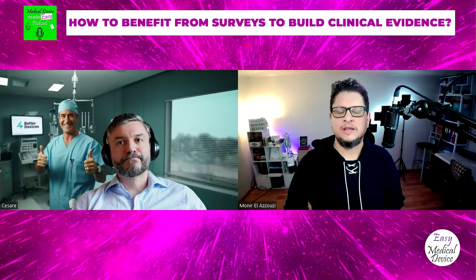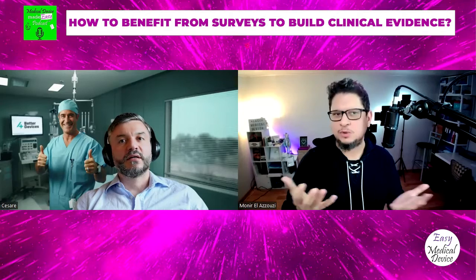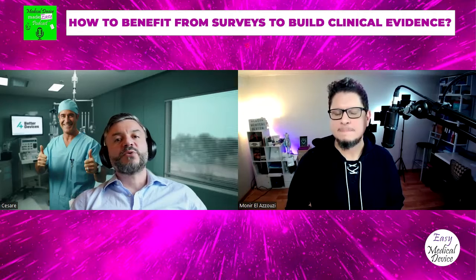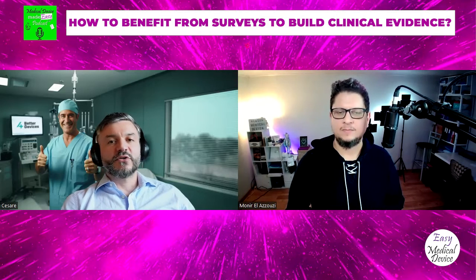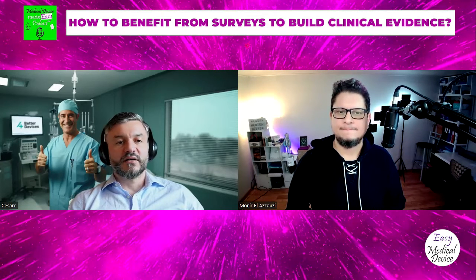So do you think a notified body reviewing a technical file for a class 3 implantable, high-risk device, like a pacemaker, as soon as they see a methodology to gather real world data through a cheap survey, as you said, will they agree on that, or will they say no? It will depend on the phase of the device. If it's going to be pre-market evidence for a class 3 implantable device, they won't accept that, plus you wouldn't even be able to collect it really. That wouldn't make particular sense.